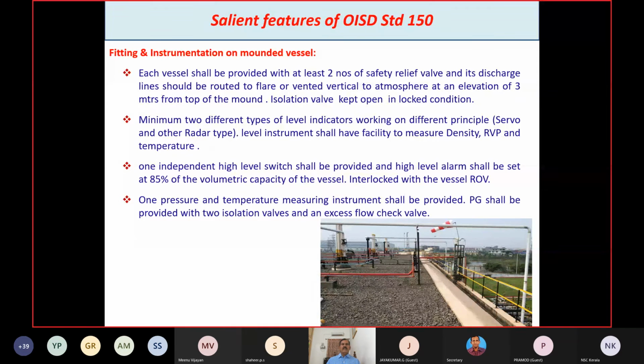And minimum 2 different types of level indicators working on different principles. One should be servo and one should be radar type. The level instrument shall have facility to measure density, vapor pressure and temperature. Apart from that, a pressure transmitter and temperature transmitter also will be available for each bullet.